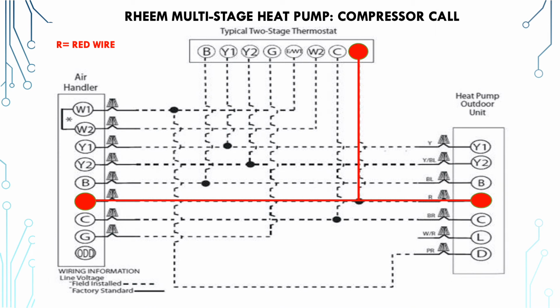So we're going to go through a tip. This is actually a schematic out of the Rheem installation manual. So we're going to discuss what we're running into. Now, this is practical and applies to nearly every system. The differences are the nomenclature that they use for different terminals or the coloring that they use on wiring inside the equipment. Our primary colors are still going to be our primary HVAC standard industry colors, but any extra wires that are needed beyond that can be used as you see fit.